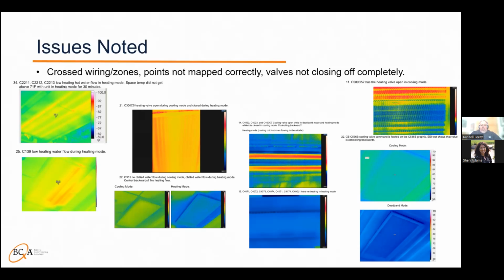So they had some valves swapped, not even tied correctly within the BAS system. And moving on to the right, there was an issue where in deadband mode, the heating mode was controlling backwards. And we actually had some heating coil flow in the cooling mode. So it was simultaneously heating and cooling at the same time. And then the one below that was in heating mode, no cooling, or no heating at full cooling. And then finally to the right, kind of another instance where we were simultaneously heating and cooling in a portion of it. And then some commands that were backward within the control system.